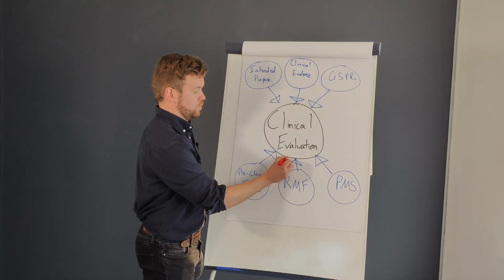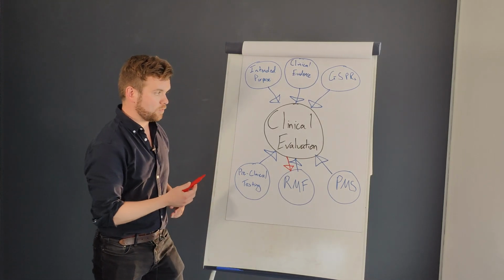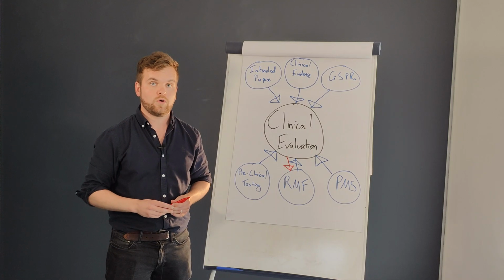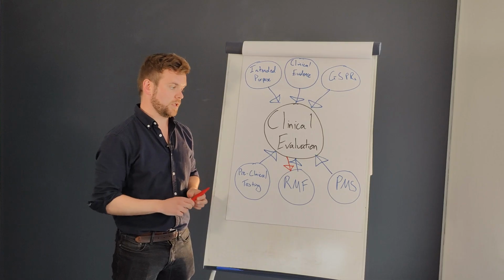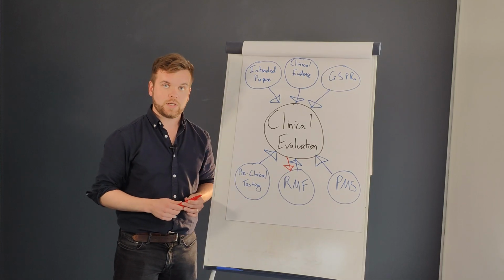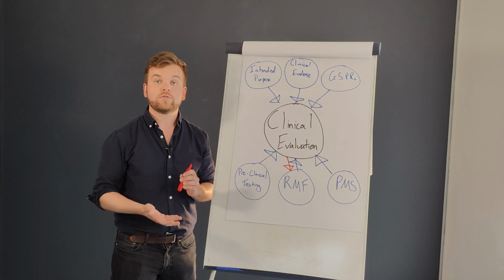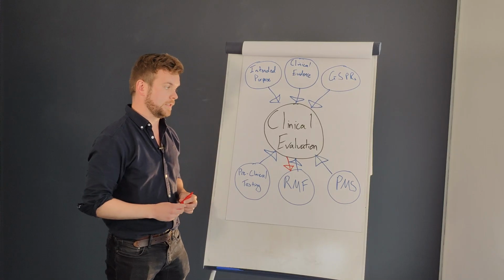specifically your risk management file. So it's absolutely essential that any risks you identify through clinical evaluation, whether previously known or brand new, are assessed appropriately in your clinical evaluation and then fed in to your risk management file going forward. So your hazards analyses and your future risk management reports need to use this information and address them appropriately.